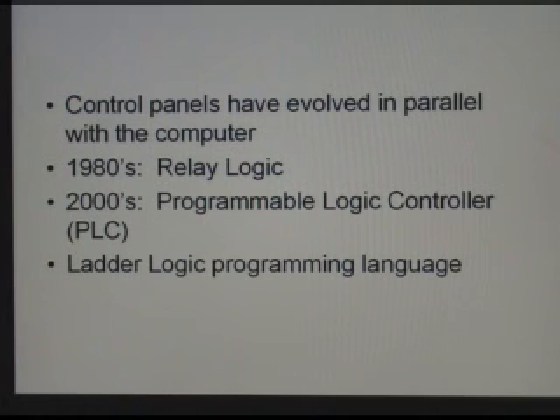The one thing that's been common, though, is the programming language, which is known as a ladder logic programming language. Ladder logic came out of the relay system, where you could see each rung of logic and exactly how each relay reacted to it. And then as the PLCs became popular, the PLC manufacturers came up with a software programming package that just mimicked ladder logic, so that the people who grew up with the relay logic could transition easily into the new PLC style.